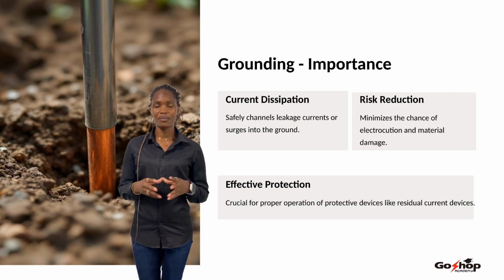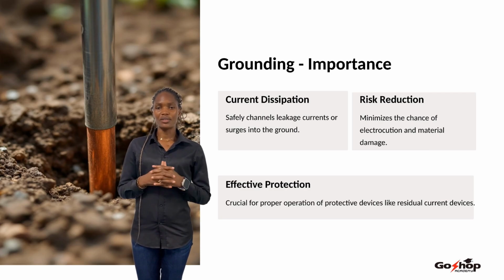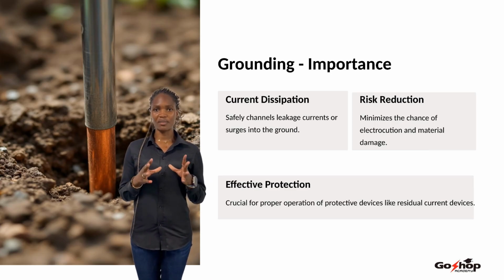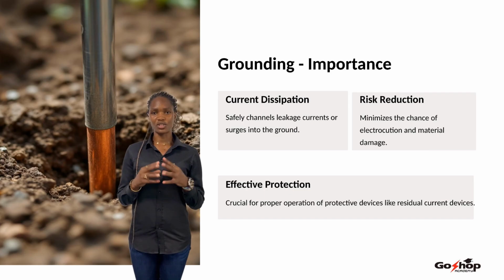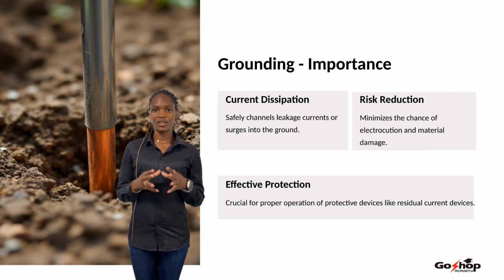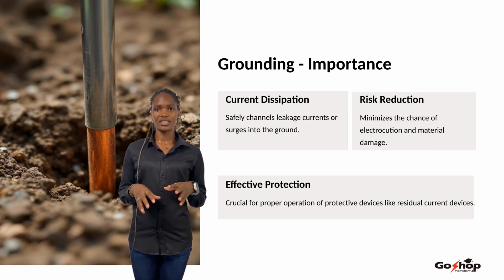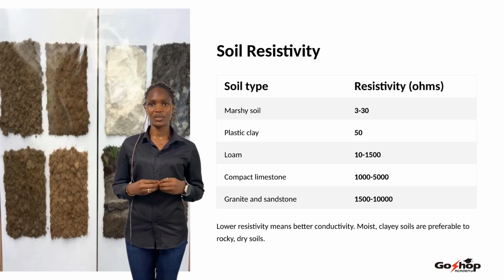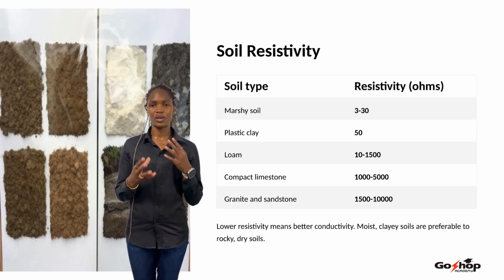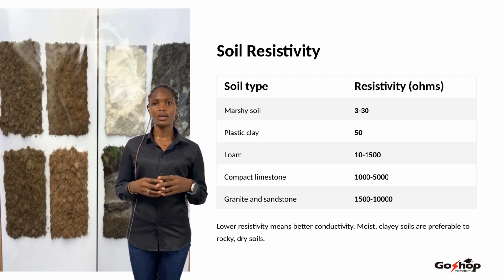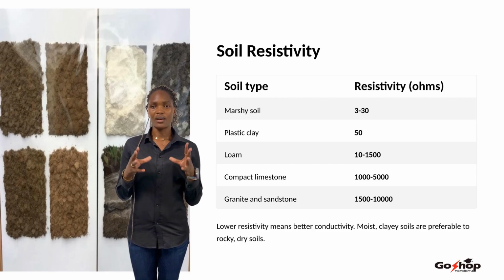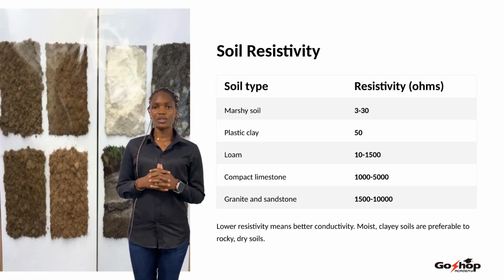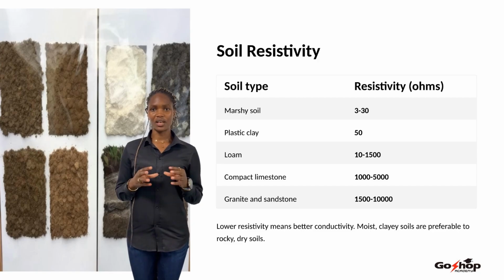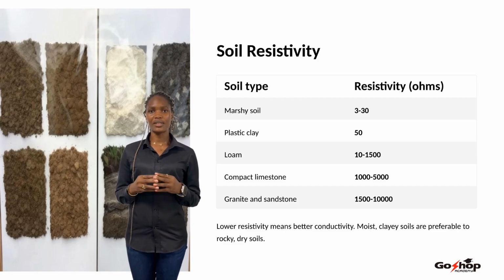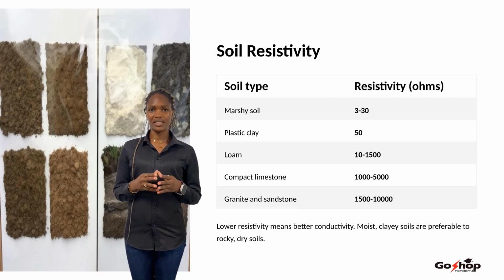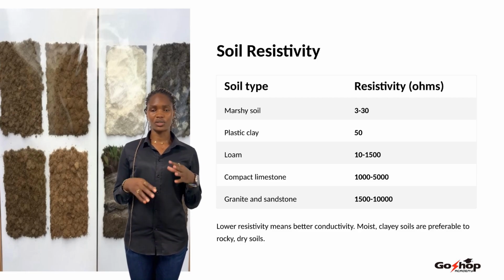Grounding allows the safe dissipation of leakage currents or overvoltages. It reduces the risk of electrocution and material damage. It is also essential for proper operation of protective devices like residual current devices, RCDs. Soil resistivity varies by terrain type. Marshy soil, 3-30 ohms, plastic clay, 50 ohms, loam, 10-1500 ohms, compact limestone, 1000-5000 ohms, granite and sandstone, 1500-10000 ohms. The lower the resistivity, the better the conductivity. Moist, clay-rich soils are better than dry, rocky soils.